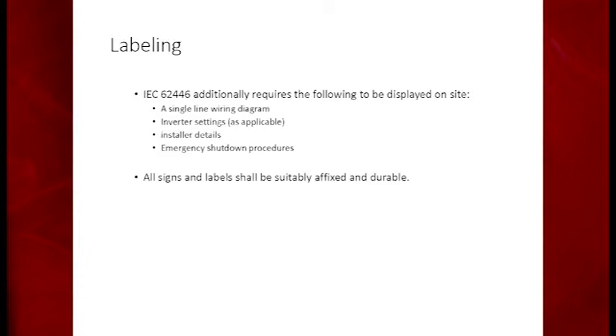By your main disconnect, there can be no more than 6 movements of the hands according to NEC for cutting off all the power going into a home or building. You must put that this has an alternate source of power, which is a PV system.